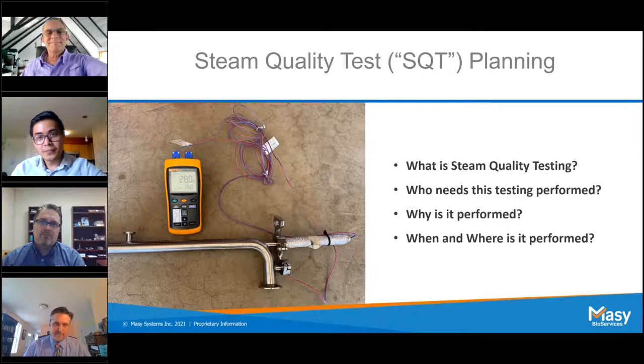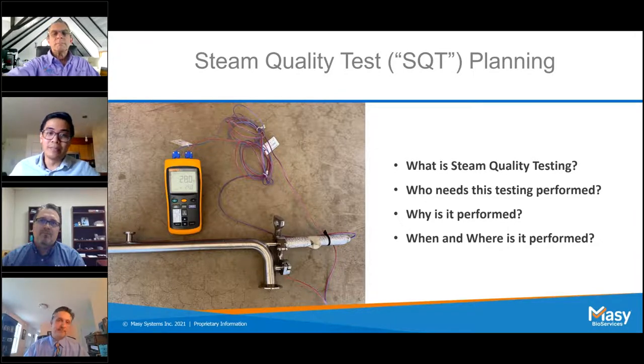And Tuan? Thanks, John. I'll be going over the when and where it is performed. We'll start with where. Typically, the steam is tested directly at the steam supply line near the generator, which can be considered the proximal port, or at the point of use of the sterilizer autoclave, which may be considered the distal port. It ultimately depends on what system you have and what access points you have available to tap into. But the conservative approach would be to test at the point of use at the sterilizer or the autoclave, as you're testing the steam right before it contacts your equipment or items you want sterilized.